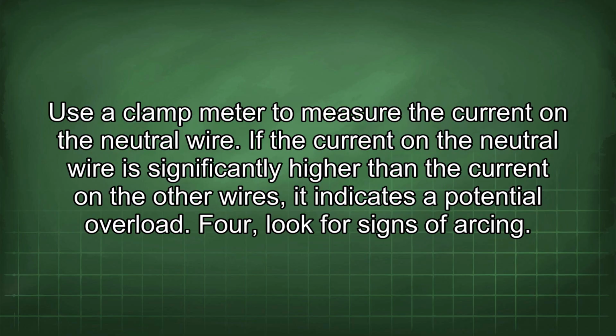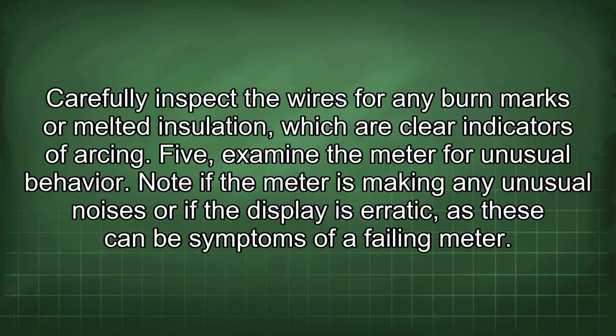Use a clamp meter to measure the current in the neutral wire. If the current on the neutral wire is significantly higher than the current on the other wires, it indicates a potential overload. 4. Look for signs of arcing. Carefully inspect the wires for any burn marks or melted insulation, which are clear indicators of arcing. 5. Examine the meter for unusual behavior.